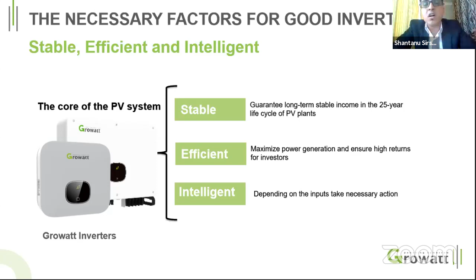So for the stability of any inverter, that inverter should be able to work in any harsh conditions. If you talk about Indian conditions, the maximum temperature that we record in the state of Rajasthan is up to 50 degrees. So the inverter should be working efficiently up to this temperature range. The inverter should have a very good working temperature range. When we are talking about the Growatt inverter, we definitely have an ambient temperature range starting from -25 degrees up to +60 degrees. And the derating of all the inverters that we are providing for the Indian market starts from 50 degrees. The second important factor is the humidity.